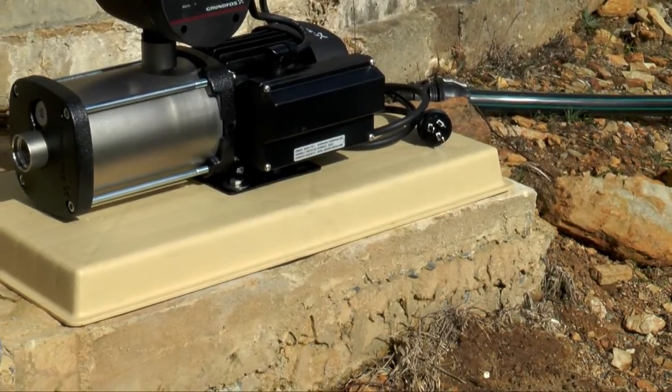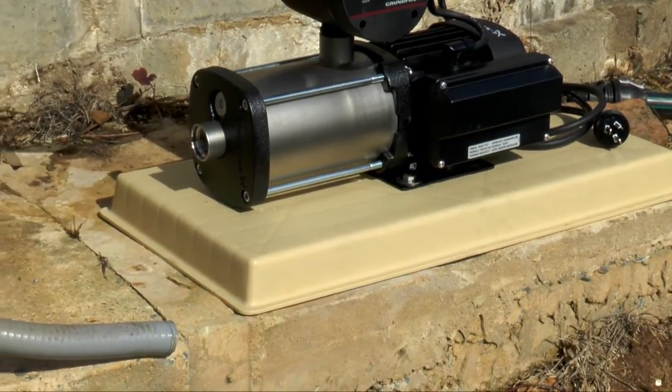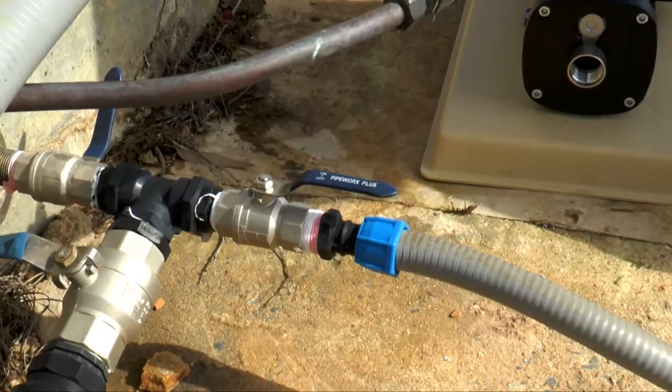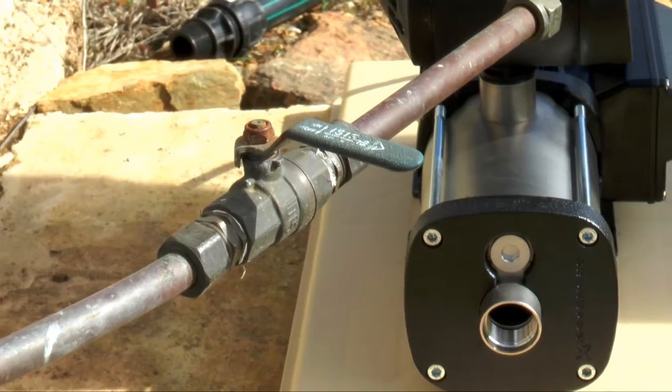When installing a Grundfos pump, ensure the pump is sitting on a flat base installed out of the weather, there is an isolation valve on the outlet of the tank and there is an isolation valve on the discharge of the pump.